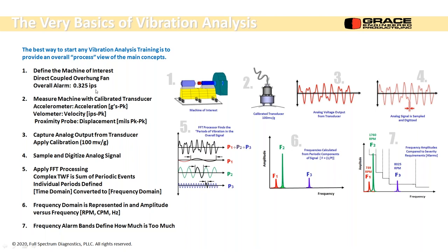This is 0.325 inches per second. So a velocity overall measurement we can put into our database and set up as an alarm, just by knowing the type of machine we have. We're going to measure with a calibrated transducer, so 100 millivolts per G. The analog signal is a voltage versus time waveform, and there are multiple wiggles in that waveform. We'll talk about that. We're going to sample and digitize that signal and turn it into a format that's not an infinite analog signal so that we can get our hands around it.